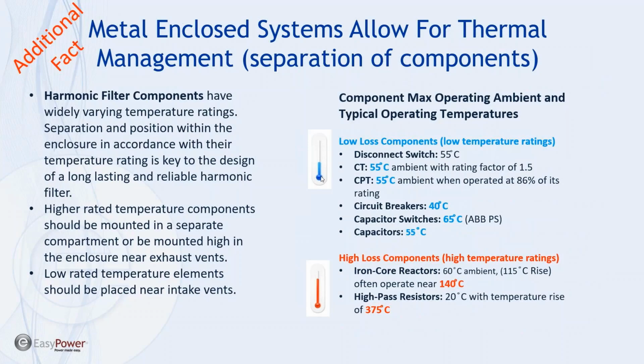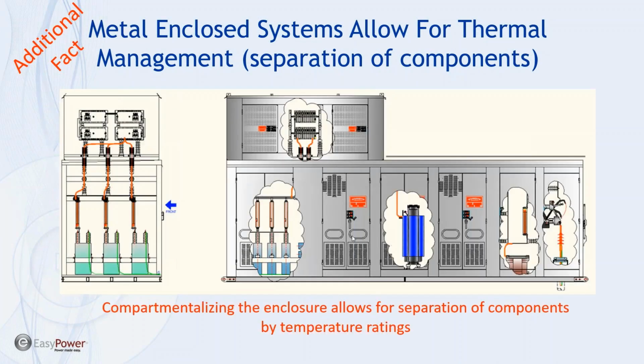The other possibility to consider is that for harmonic filter banks, we can do what we call thermal separation. We have components that are rated relatively cool. These include disconnect switches, CTs, PTs. These all have temperature ratings in the 55 to 65 C range. And then there are the high loss components, which include high pass resistors, which run very hot, and iron core reactors that also run in the area of 140 C. Typically, iron core reactors have a temperature rating of 220 C for the insulation system. So inside our enclosure, we have low loss components with relatively low temperature ratings in that 50 to 55 C range, and high loss components, at 375 C for resistors and 140 C for iron core reactors. So if I flip to the next page, you can see what we can do.